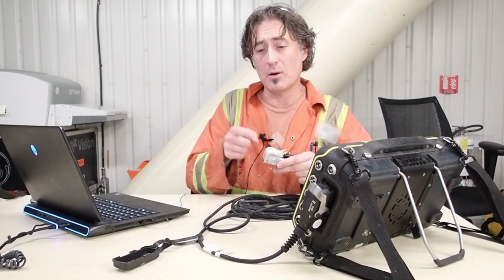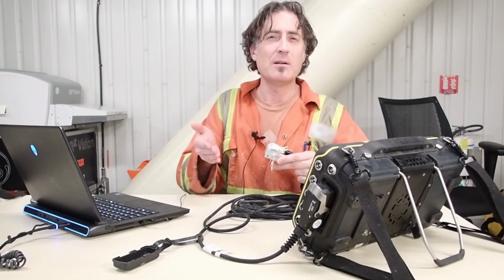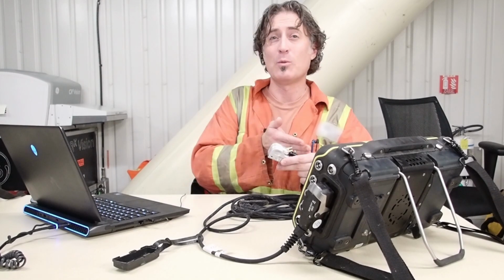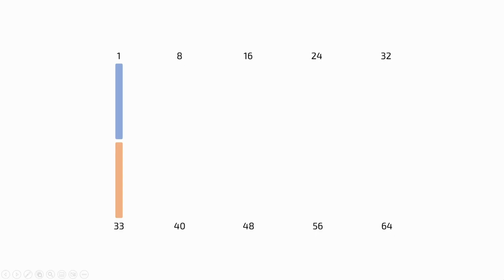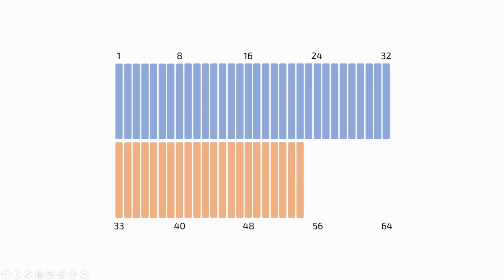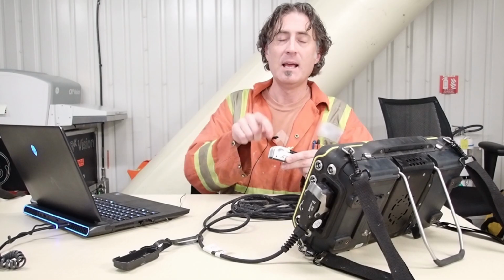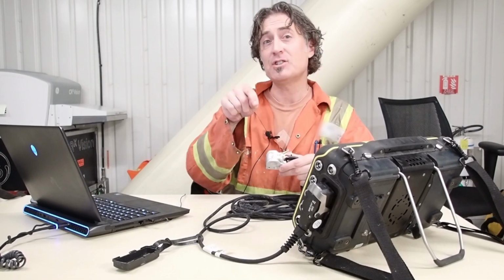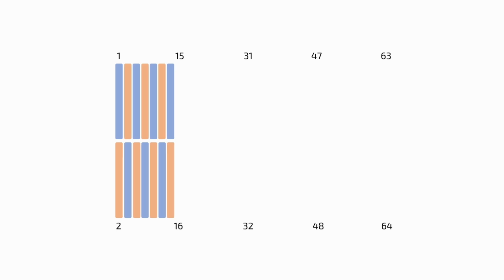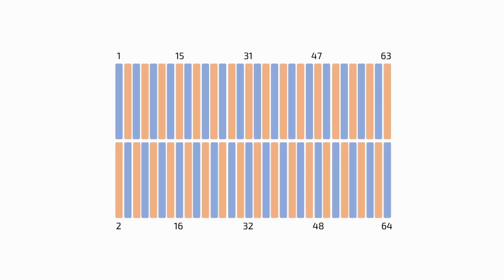This particular model of corrosion transducer is wired differently than what you might think a normal DLA would be wired. Normally, you'd think, say, elements 1 to 32 would be on one side and 33 to 64 would be on the other side. That's not the case. In this one, they've actually got the even elements on one side and the odd elements on the other side.